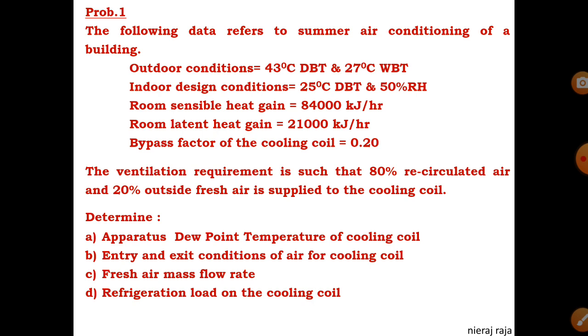Depending upon the number of occupants and what activity is going on in the room, occupancy also dissipates heat. Every activity, whether it's a gym, a bank, or a house, releases a particular heat. By considering all those heat gains, we classify them as sensible heat and latent heat. The sensible heat is 84,000 kJ per hour and latent heat is 21,000 kJ per hour. Sensible heat only changes the DBT, while latent heat is responsible for changing the humidity or moisture content.